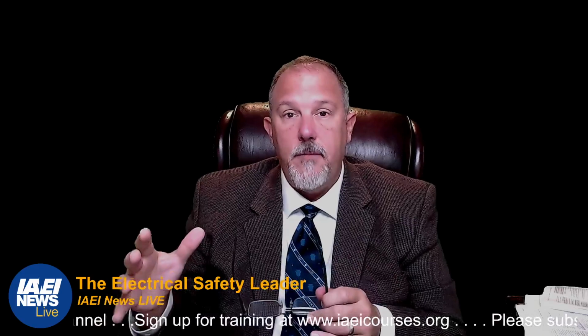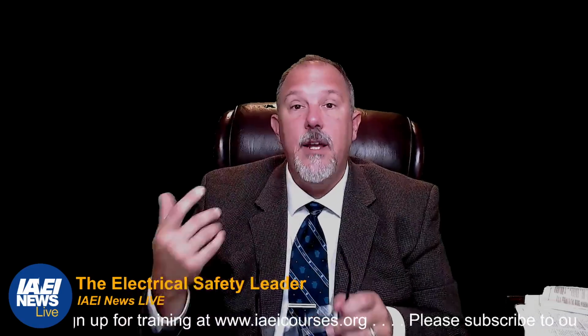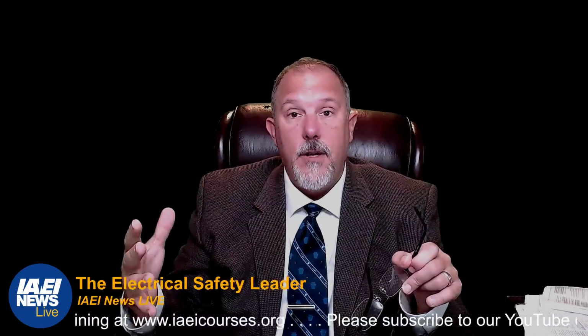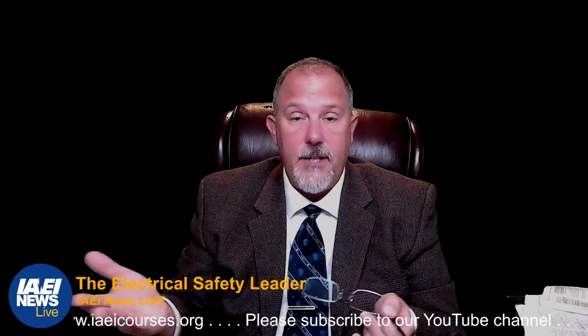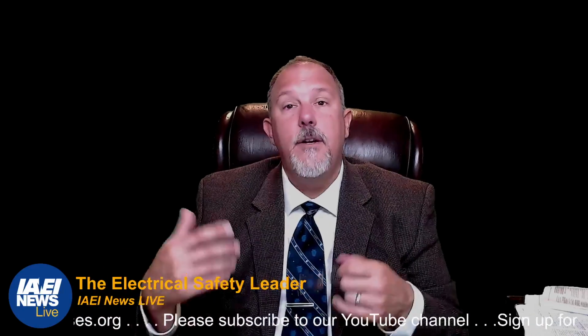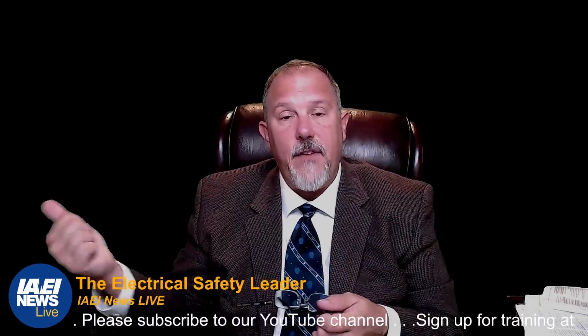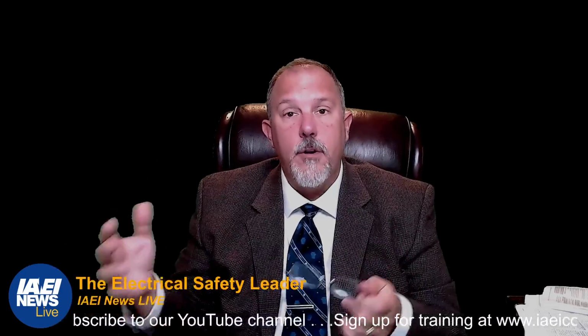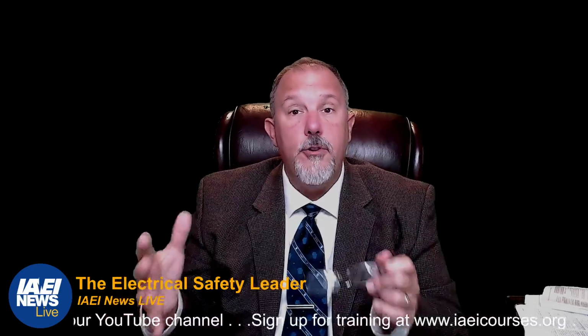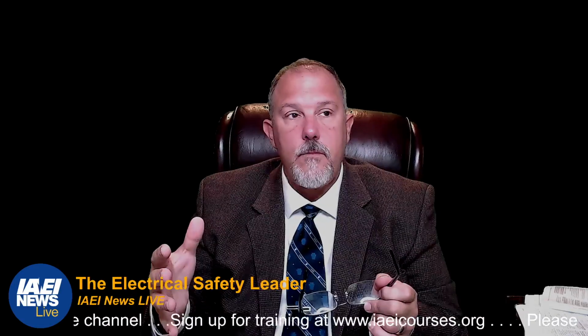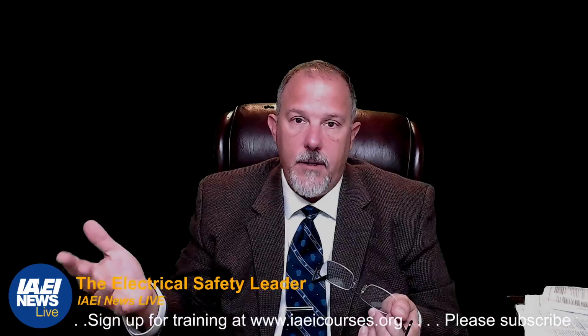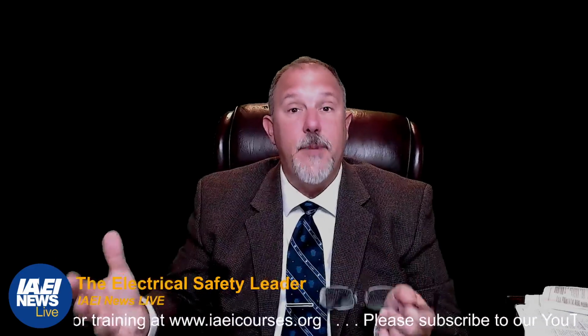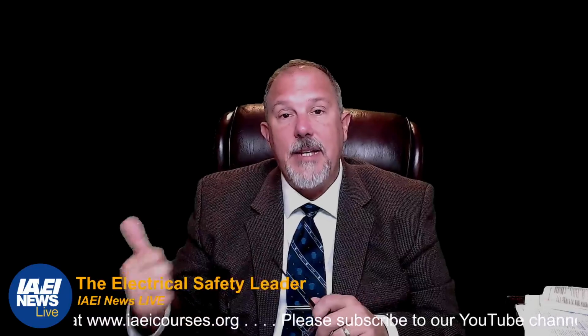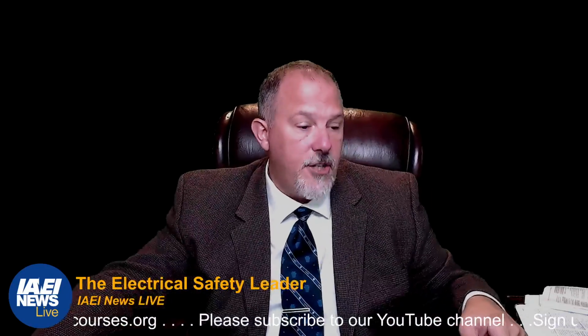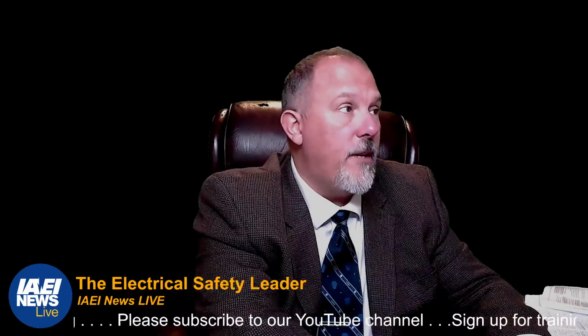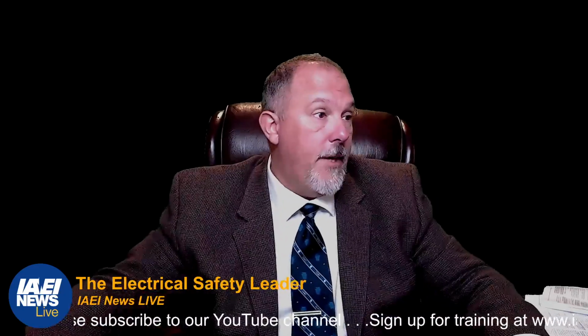In some cases, you may be able to say, look, we're going to take this out of service, replace the enclosure, and use the interior. The interior is in great shape. You can take the interior out, put another enclosure in place, talk to the manufacturer, get the right enclosure for the panel board, and bring the enclosure back up to speed. In some cases, you may have to replace everything, depending upon the environment. Go take a look at NFPA 70B, and 70B just became a standard, or it's going to become a standard here shortly.